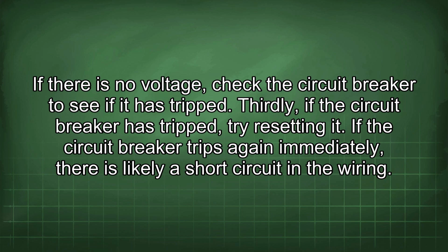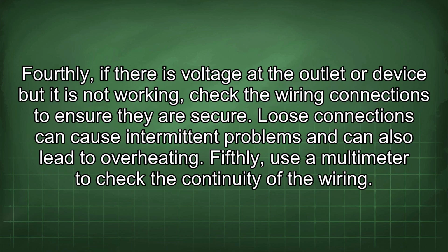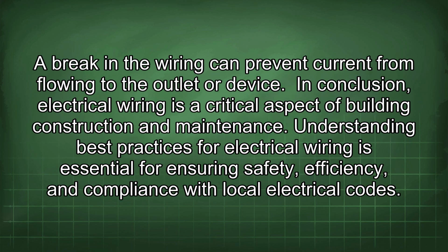Thirdly, if the circuit breaker has tripped, try resetting it. If the circuit breaker trips again immediately, there is likely a short circuit in the wiring. Fourthly, if there is voltage at the outlet or device but it is not working, check the wiring connections to ensure they are secure. Loose connections can cause intermittent problems and can also lead to overheating. Fifthly, use a multimeter to check the continuity of the wiring. A break in the wiring can prevent current from flowing to the outlet or device.